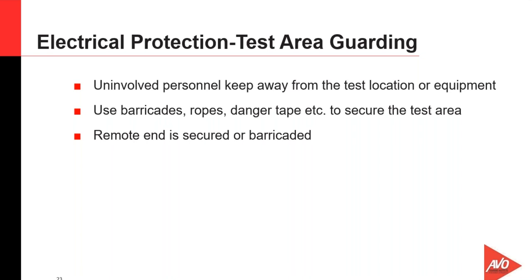And most of the time, this is going to require some type of guarding system, either the use of barricades or ropes or simple danger tape works well. Caution tape does not work. Caution tape is, we normally consider that the duck under tape. The danger tape would be danger high voltage keep out. That works real well for most people.